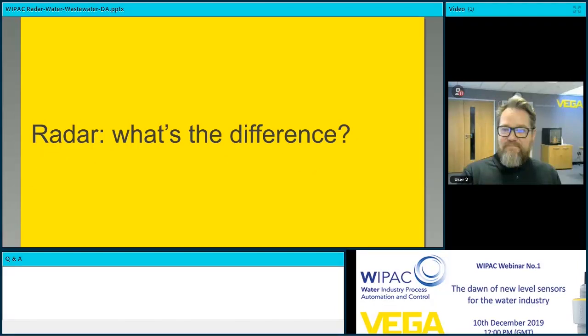So what's the difference? Well, if we look at the incumbent technology, ultrasonic, it's a good proven technology. It's also still manufactured by Vega for now, and we've been doing that for over 40 years. That's because many years ago, we regularly discovered its limitations and decided to look for an alternative. In many industries, we saw issues mainly with accuracy and performance, like wandering measurement readings on vapors, solvents and fuels, in summer or in winter, depending on if there's sun on the tank tops or not, creating more or less vapors inside the vessel, and temperature issues on the transducers themselves.